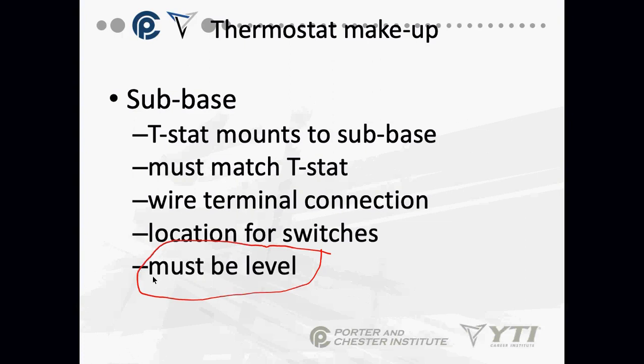For digital thermostats, it's an appearance situation. From an operational standpoint, they don't need to be level. But from a customer appearance standpoint, if that thermostat is not level, I can guarantee you're going to get a callback on it. Okay, callbacks is an evil word in this industry. But you're going to get a callback on it because the homeowner will go nuts over a thermostat not being level. They'll see it every time they walk past it or when they look across the room.